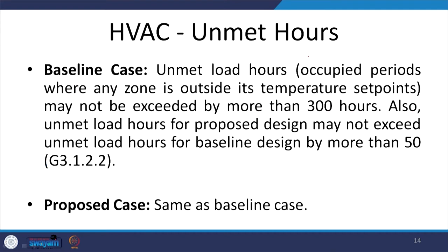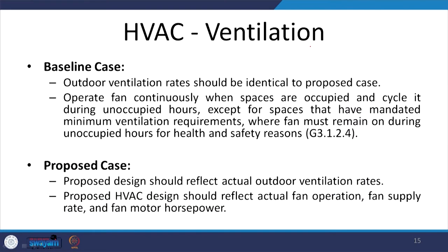In case of HVAC unmet hours, the unmet load hours for the base case will not exceed 300 hours, and this varies for different codes and standards. However, when we are talking about the proposed case, it will be kept the same as the baseline case and there will not be any variation in this. So, this remains more or less the same. In ventilation, the outdoor ventilation rates in both baseline and proposed case will be the same, where it will reflect the actual outdoor ventilation rate.